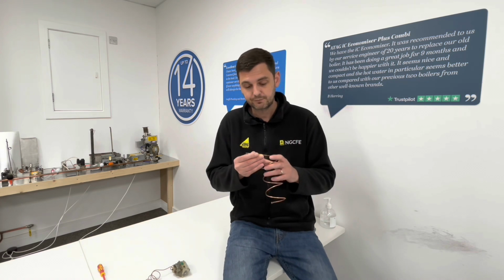Whenever you see a thermocouple, you will have a thermoelectric valve, and this is a thermocouple. All it is is two dissimilar metals that, when heated via either a pilot light or a burner, will create an electric current, and the electric current will travel down the coil and then to a thermoelectric valve, and it will hold the thermoelectric valve open by energizing a magnet. In the same way, when the flame is extinguished for whatever reason, this will start to cool down and will stop producing the electrical current. At some point within our allowance for our FSD, the electric current will stop energizing the magnet and the valve will spring closed, stopping the flow of gas. So that's a thermocouple. We're going to see a lot of them on our controls board.